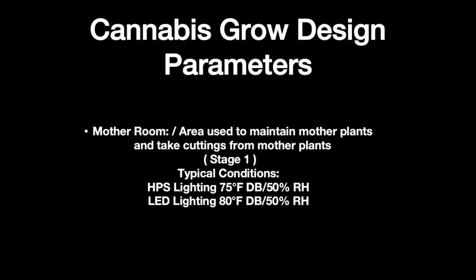Generally your mother room, like I said, is where they maintain their genetics. And they take cuttings from these mother plants because what they're trying to do is replicate the genetics of that plant and continuously get the same thing. General conditions that you're looking at, if you're looking at the high pressure sodium lights or metal halide lights, generally we're seeing those rooms designed at like 75 degrees and 50% relative humidity. If they're doing it with LED lights, generally they'll run the temperature a little warmer, up around 80, but then they'll maintain somewhere in the range of 50% relative humidity.